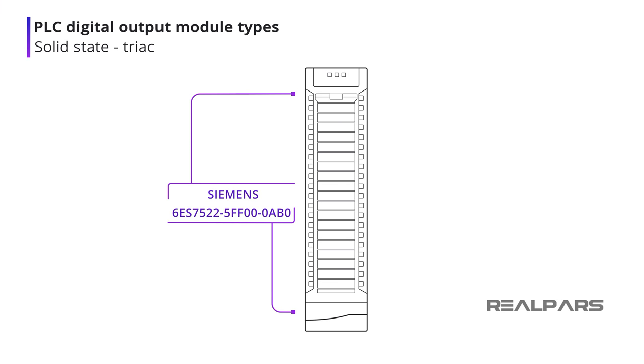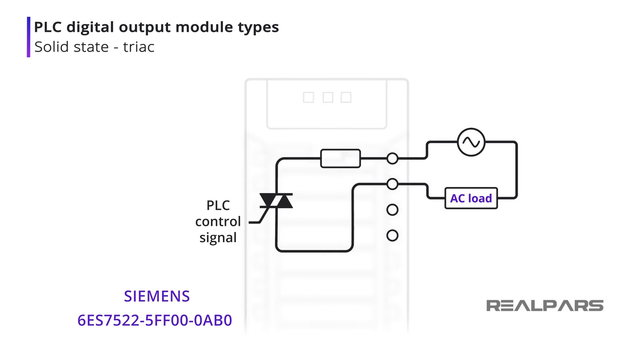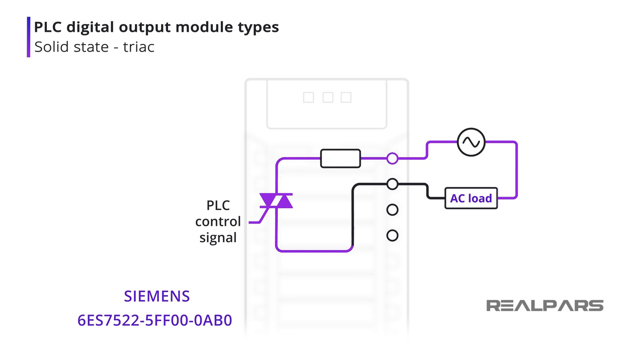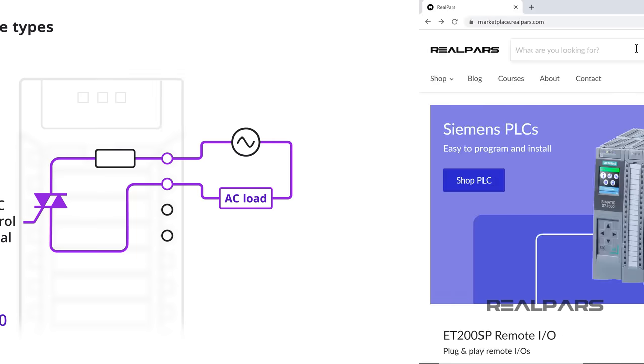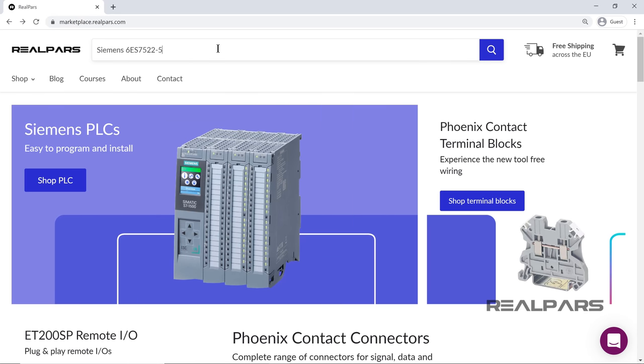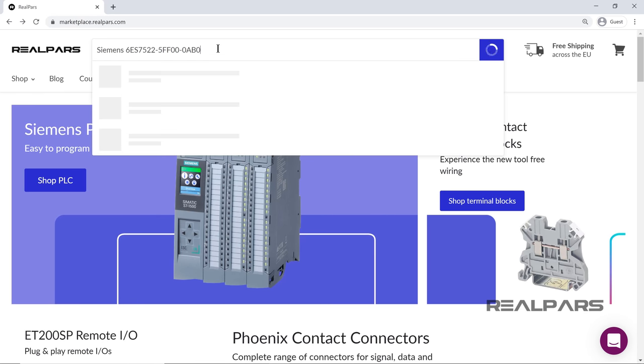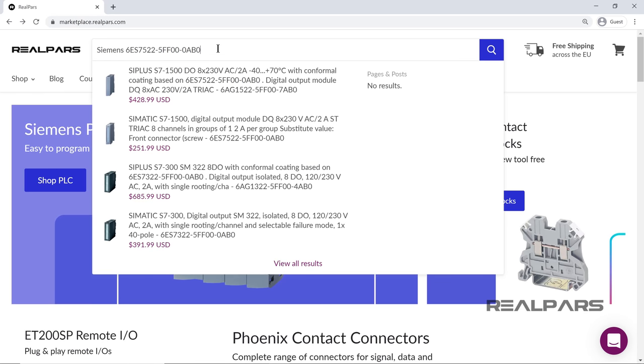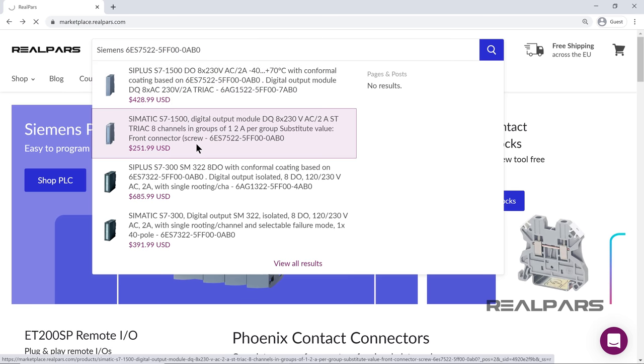The Siemens 6ES7522-5FF00-0AB0 is an 8-output TRIAC output module. A TRIAC output module is capable of controlling AC loads where transistor output modules can control DC loads only. When the PLC signal is applied, the TRIAC will turn on and provide an alternating current path for the load. You can find the link to order this PLC module in the video description as well.